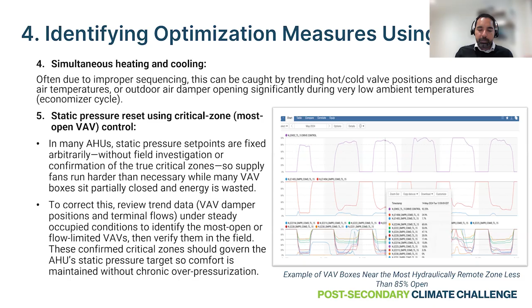Typically, the air handling unit systems are set up in a way that the static pressure set point is arbitrarily set in the system, and the VFD is controlled using that static pressure set point. And typically, those are set at a higher value than they're supposed to be. So understanding what your static pressure set point should be for each system lets you optimize it to a point that reduces your VFD speed not only during the unoccupied period, but also during the occupied period as well. So it helps you, if you're a Class A customer, as an example, on your global adjustment rates as well.